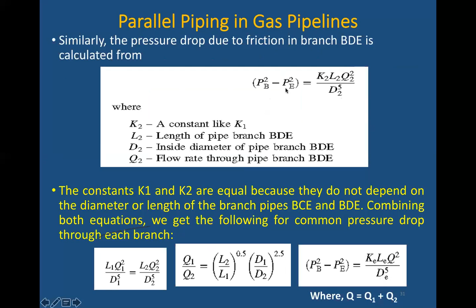So I can give one hint. You see, there is the pressure drop in one pipeline. Once you are taking the equivalent, P equal to P1 plus P2. Once you do the simplification, you will get L equal to L1 plus L2, in case of series. And how are you getting LE2? Go to the liquid pipeline, you will get this type of form. When you have LA and LB, you get L equal to LA plus LB into DB by DA to the power 5. Now just change A and B to 1 and 2. So L equal to L1 plus L2 into D2 by D1 to the power 5. So try this one.